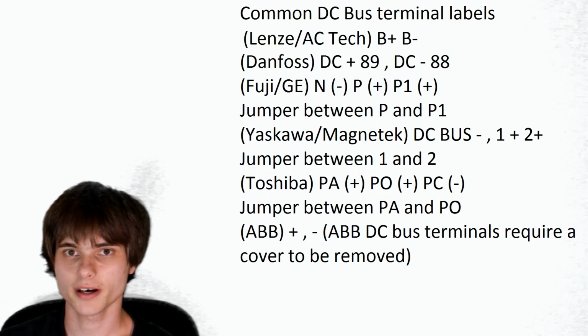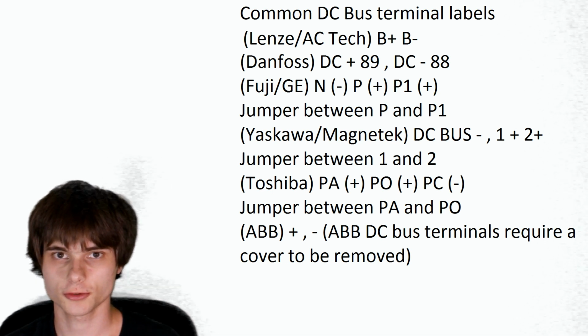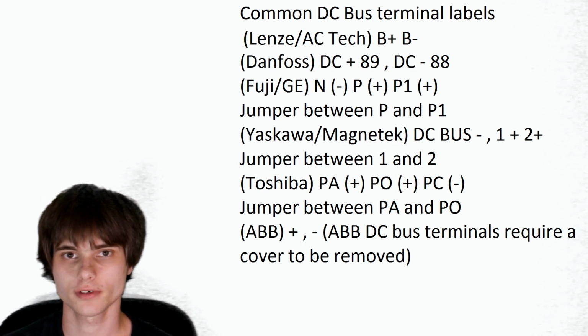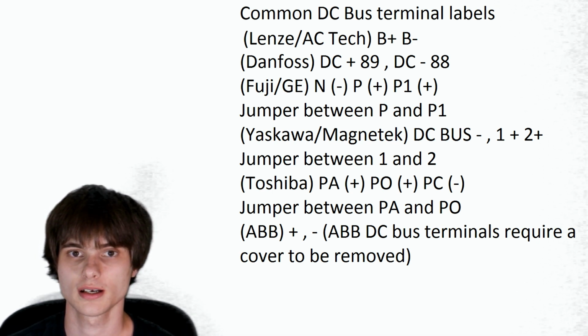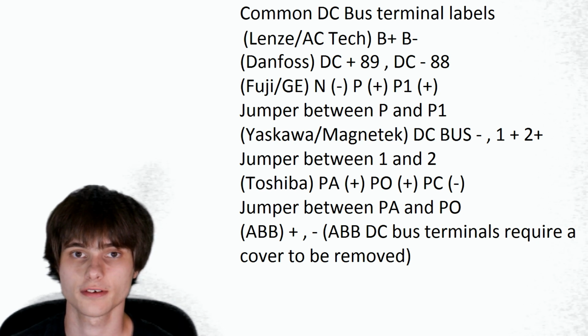So guys, that's about it. Just real quickly again, if you are trying to operate a variable frequency drive from direct current, this is what you're looking for. You're looking for a newer VFD, you're looking for positive and negative terminals, or any terminals that say bus, DC bus, some say B positive, B negative.